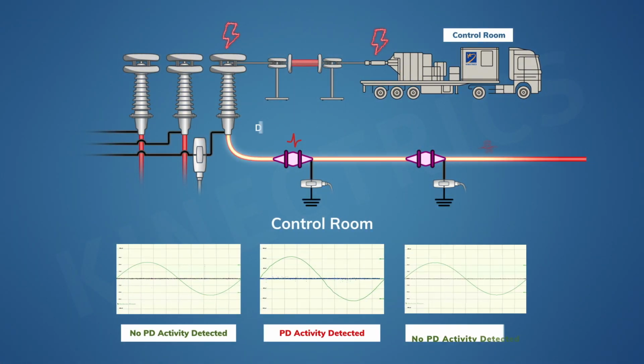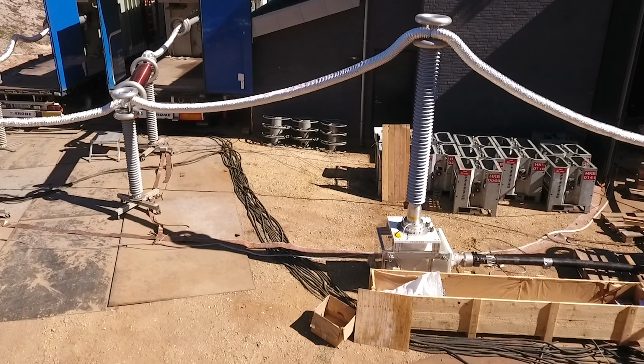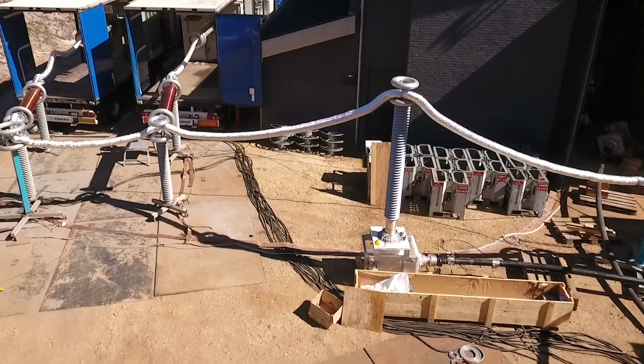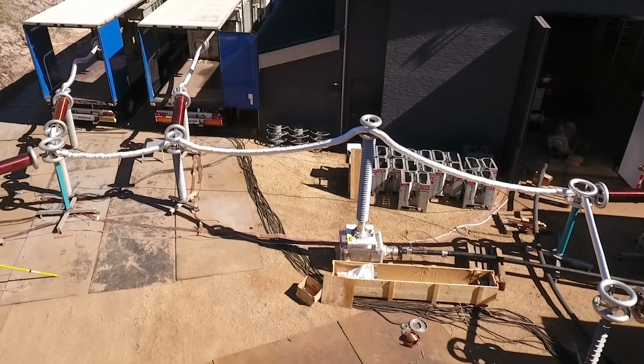So I've talked about the voltage test and partial discharge, but there's a whole range of other tests that may be required. For instance, there are specialised tests required in the UK market. There are specialised tests for offshore cables and so on. It's safe to say that if the test appears in a specification, we can do it. We'll either have or can devise a way of carrying out whatever test you require on a cable system. You can be assured after our test, we've either pinpointed a problem or qualified the cable as being reliable.